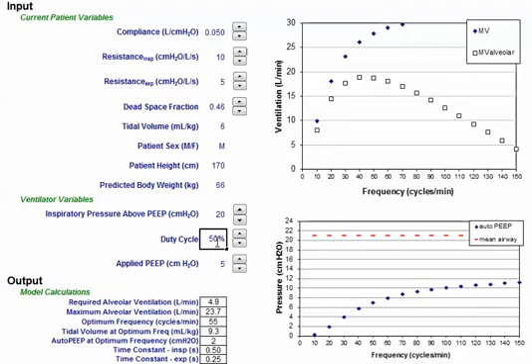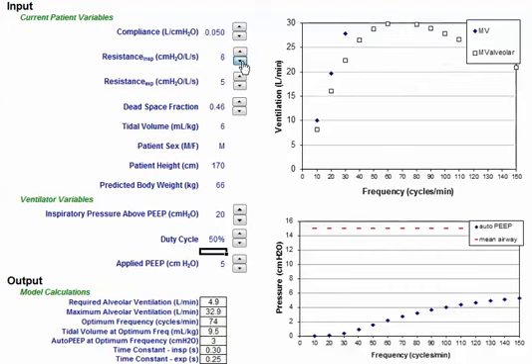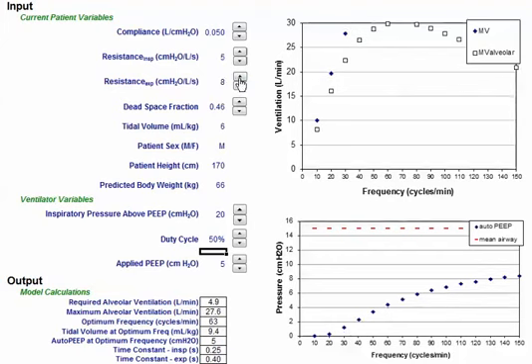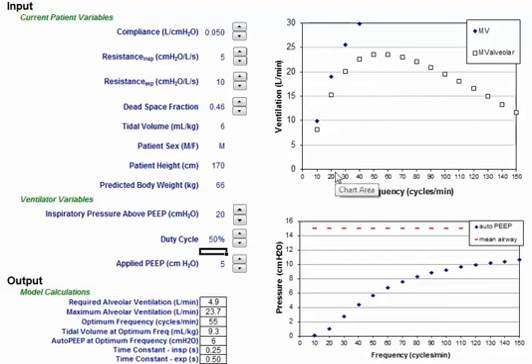I'm going to change that back to 1 to 1, my optimal setting when both resistances are equal. However, what if my expiratory resistance is more than my inspiratory? As you notice, on a 1 to 1 IE ratio, I'm not attaining my max obtainable minute ventilation.